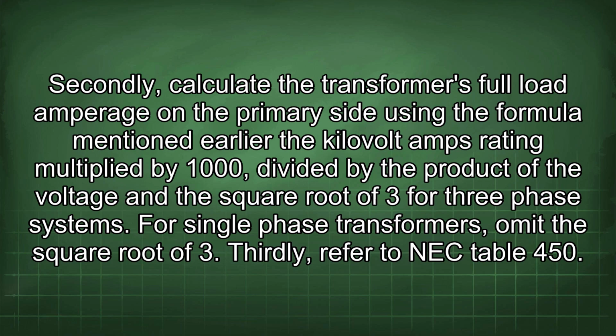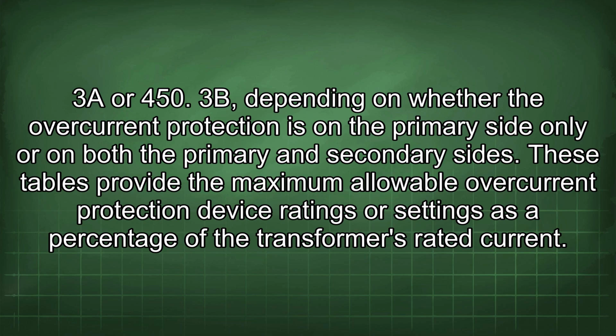Thirdly, refer to NEC Table 450.3a or 450.3b, depending on whether the overcurrent protection is on the primary side only or on both the primary and secondary sides. These tables provide the maximum allowable overcurrent protection device ratings or settings as a percentage of the transformer's rated current.